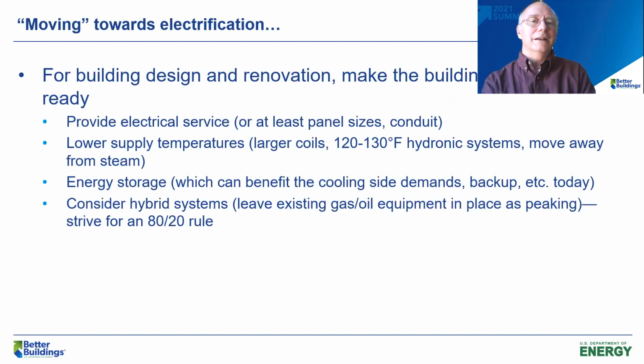Think about, on the actual emitter or at the end use, lowering that needed supply temperature. I recently worked with a school that got rid of their steam system, which was 70, 80 years old. It was on the brink of failure. It was very expensive to maintain. And they wanted to switch to hydronic hot water.